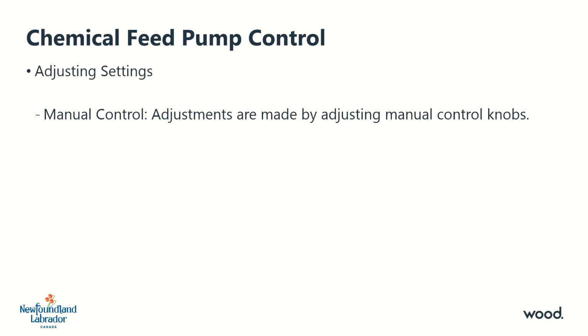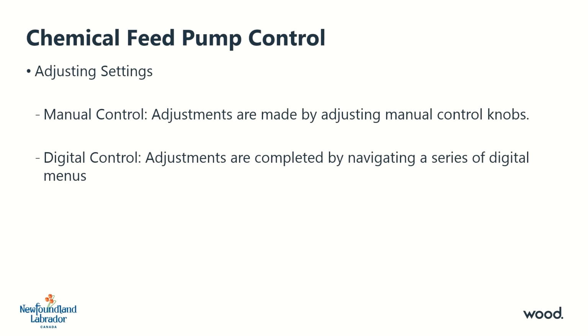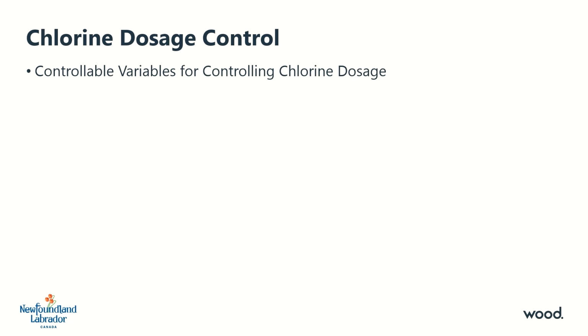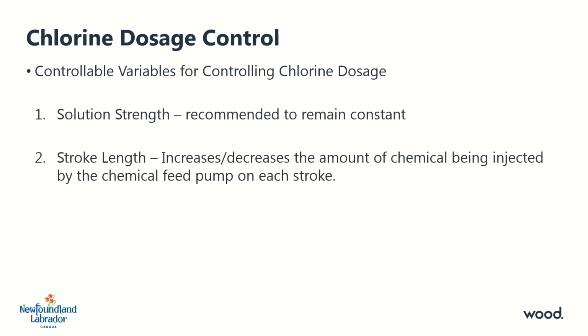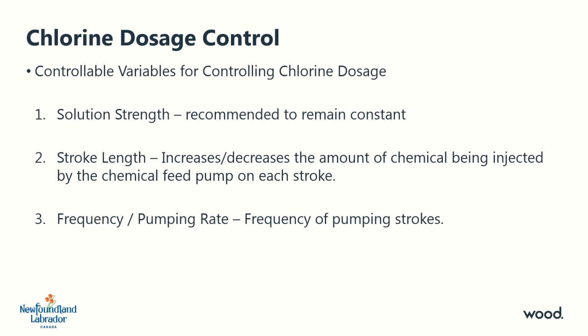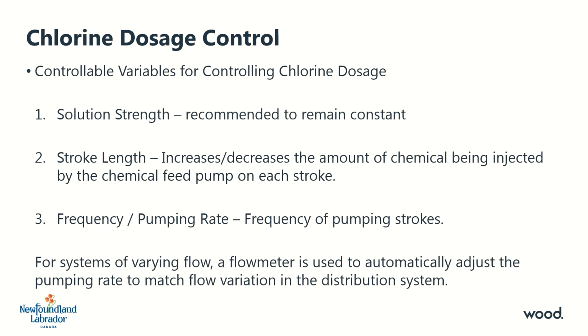Chemical feed pumps can be controlled manually, whereby settings are adjusted by control knobs, or they can be digital, whereby adjustments occur through a series of digital menus. There are three options for controlling chlorine dosage: solution strength, stroke length, and frequency. The most effective way to operate is to keep two of these factors constant and have one variable. It is recommended that the solution strength and stroke length be held constant because in most systems, frequency is controlled by a flow meter, which is constantly changing with flow.